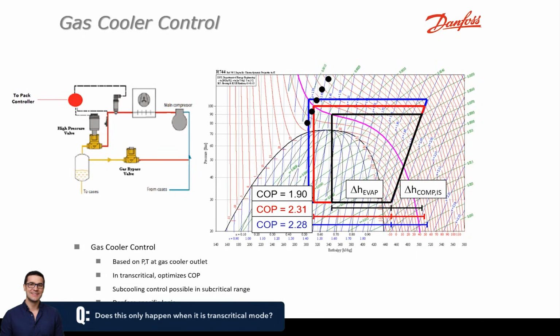That's correct. That's a very good point. In subcritical mode, we're operating almost like a standard HFC system, where we try to get a few degrees of subcooling out of the system. But because we're in the supercritical range, we've got no condensing happening per se. So we have to treat things a little differently, and that's where the COP comes into play. When we're subcritical, we're operating this valve just to try to get a few degrees of subcooling out of it.